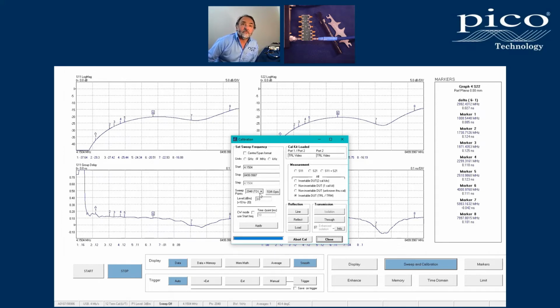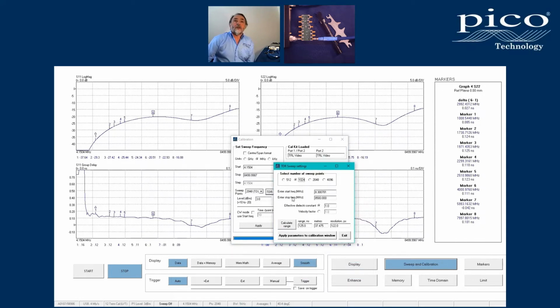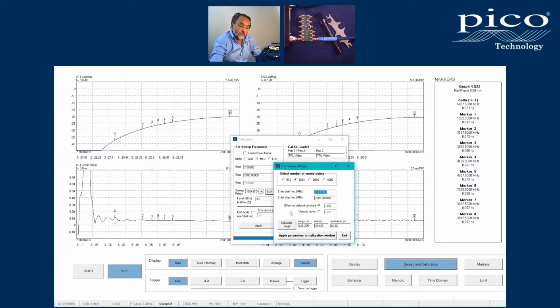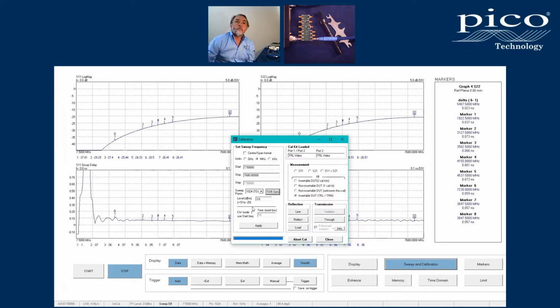It's a TDR calibration that we're doing. I'm going to keep my 1024 points. I'm going to lower that to 7. Okay, so apply. We've applied our new span. We can now begin a calibration within the range of our cal kit.